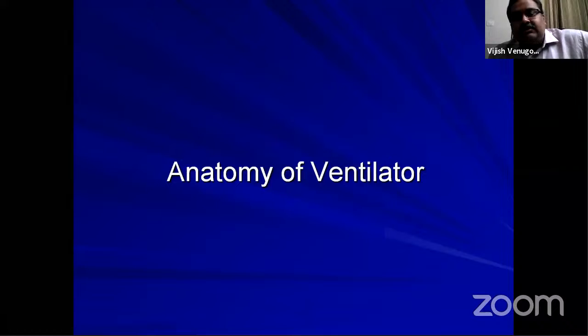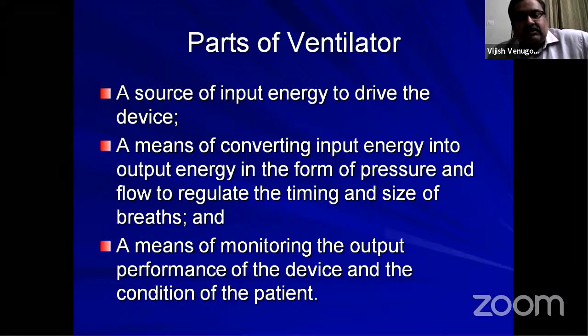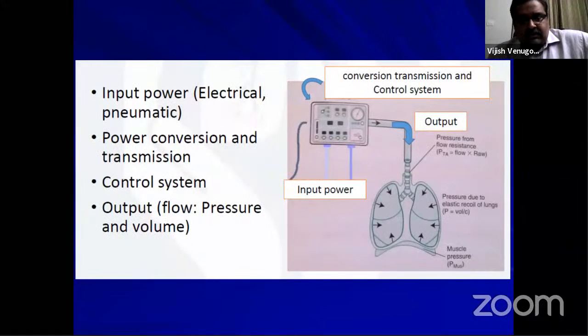However, we'll move into the anatomy of a ventilator. We'll just rapidly go through the anatomy of a ventilator. There are three important things that should be there in an automated ventilator: a source of input energy to drive the device, a means of converting this input energy into output energy in the form of pressure and flow to regulate the size of breaths, and a means of monitoring the output performance of the device and condition of the patient. So in short, there should be an input power device, a power conversion and transmission system, a control system, and an output. That is usually by flow sensors.